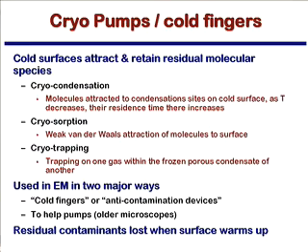There are three types of things that can happen. You can have cryocondensation. The idea there is that the molecules that are floating around will condense on sites on that surface, and you can increase the time that they'll stay there by having a colder and colder surface. You can have cryosorption. That's where van der Waals attractions hold the molecules, or you can actually have the molecules trapped by the frozen bits that are there on top of the cold finger itself.